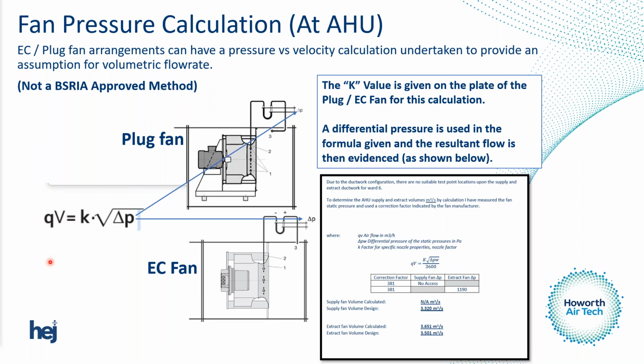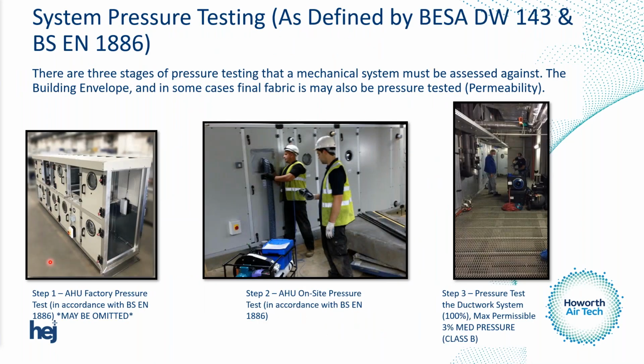So we do all that work to get the air through the air handling unit and make sure that it's being delivered where we want it to be delivered. But there's 3 steps that need to also be considered in terms of permeability testing of the air handling unit. So within HTM 03, there's a standard that's referenced, BS EN 1886, and these are the stages that it relates to. The first step, step 1, is the AHU factory pressure test. Now, I'm working on a project at the moment of 2 UCV operating theatres that we're going to validate further down the line.